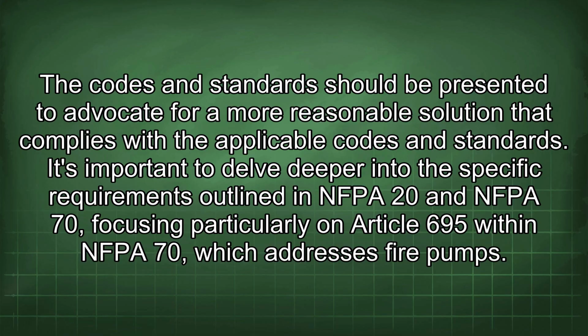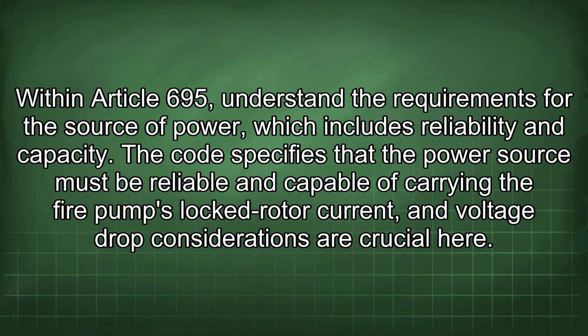It's important to delve deeper into the specific requirements outlined in NFPA 20 and NFPA 70, focusing particularly on Article 695 within NFPA 70, which addresses fire pumps. Within Article 695, understand the requirements for the source of power, which includes reliability and capacity. The code specifies that the power source must be reliable and capable of carrying the fire pump's locked rotor current, and voltage drop considerations are crucial here.